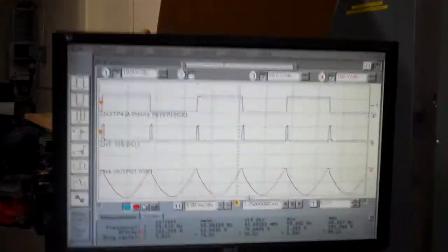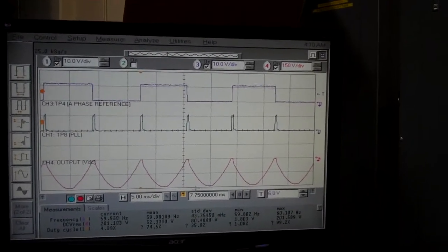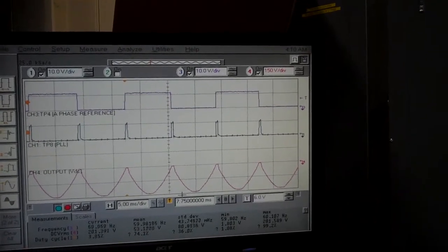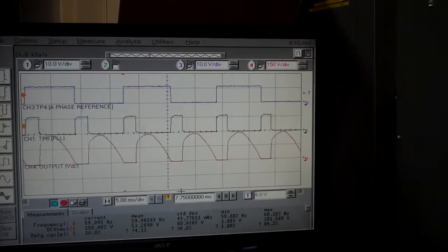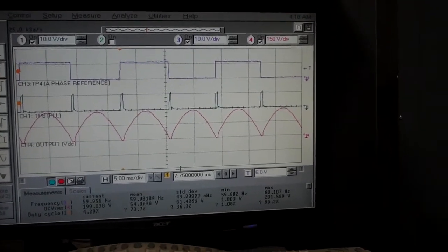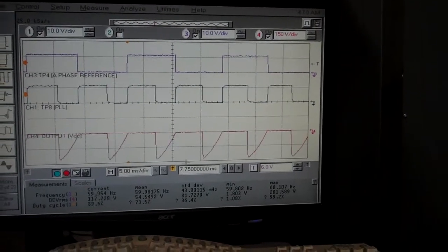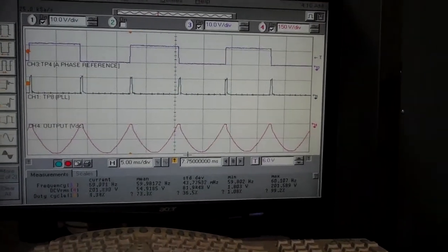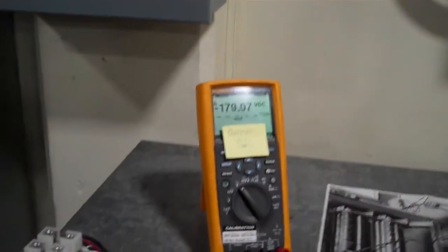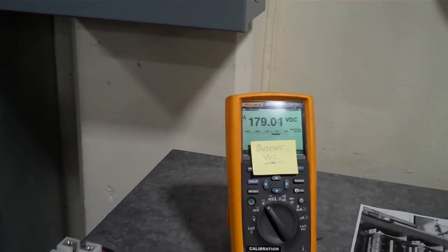Got the unit in. One thing that we can do is we can have the polarity command while the unit is enabled. So let's try that out. So we see how the unit soft starts, and then it changes the polarity, and then transitions, and we get roughly the same output. Here we have 178, 179, and if we do it again, we get 179.